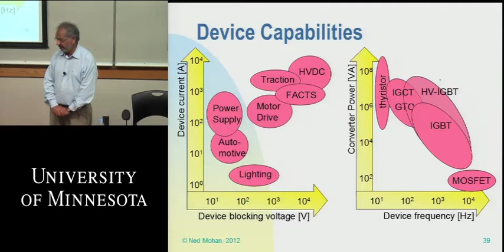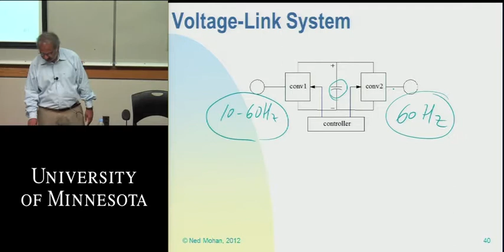So what do these power electronic interfaces do? Here you have, say, 10 to 60 hertz from the wind turbine, and here you have 60 hertz. One very common way to accomplish this is to first convert this variable frequency voltage to a DC voltage across a capacitor. Once you have this DC voltage, you can chop it up to synthesize the 60 hertz output. So you go from variable frequency to DC, then chop it up and convert it to 60 hertz—that's basically the nature of these converters.